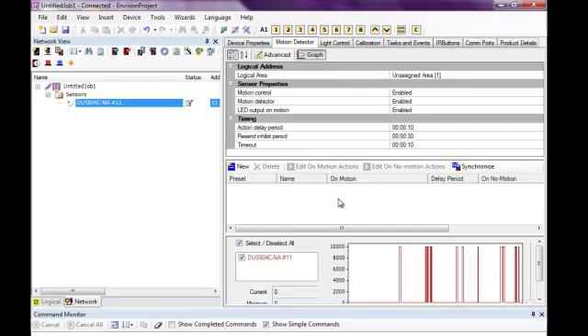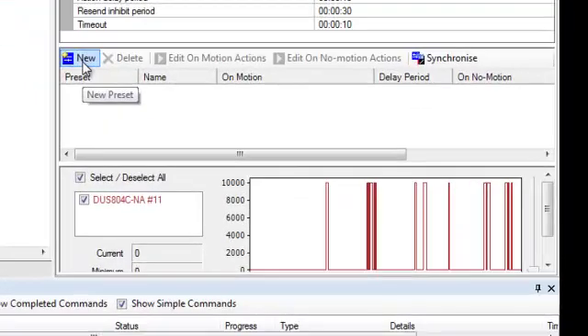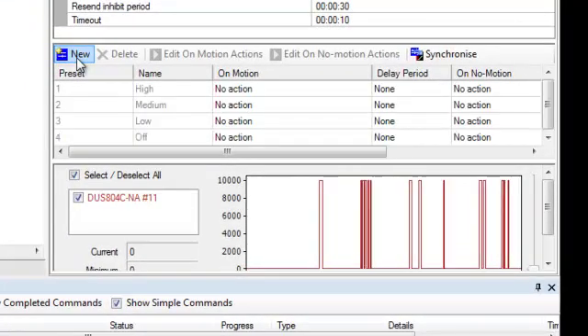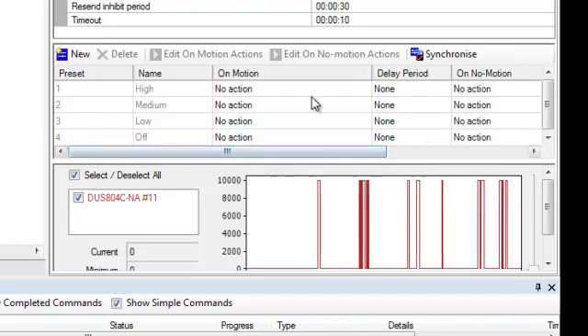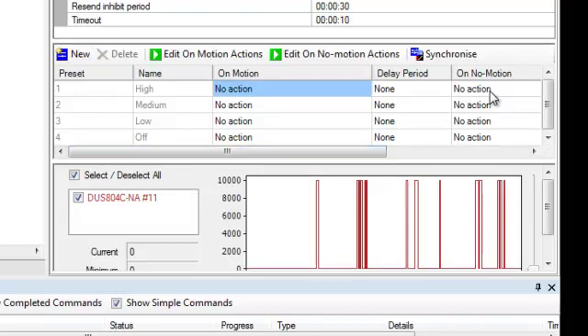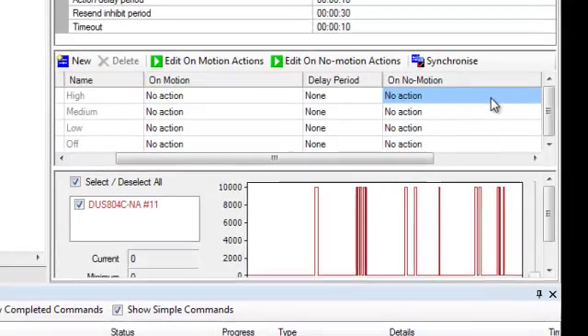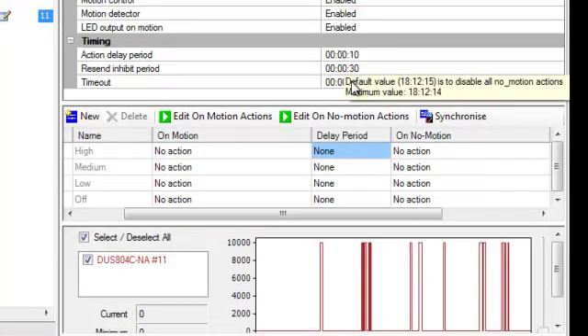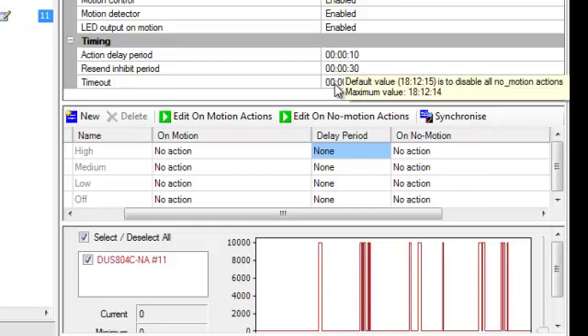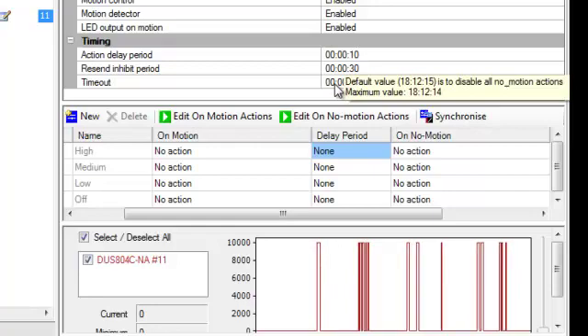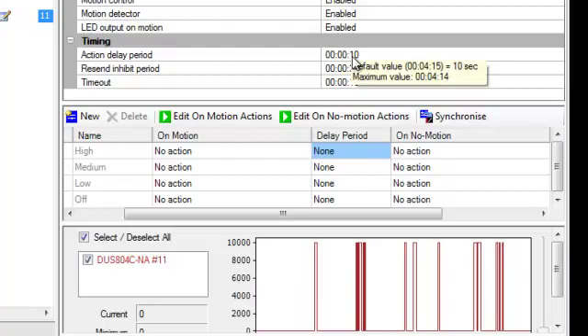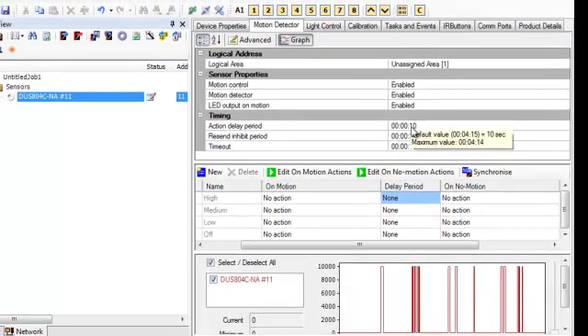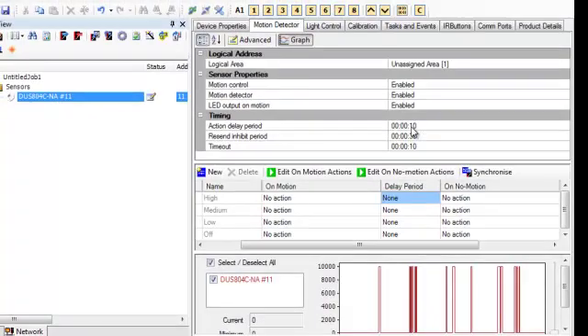Some of the other advanced things I can do is actually create occupancy or vacancy based off of a preset. So I'd go ahead and enter my preset numbers in here, so I have presets 1 through 4, and how I want it to act on motion or on no motion. Obviously I can adjust those delay periods, so I do have my actual physical time out, so how long until this light turns off on me. But I can also do other things to where if I have a switch across the room, I can turn off and disable the sensor just long enough for me to get out of the room so the lights don't turn back on.